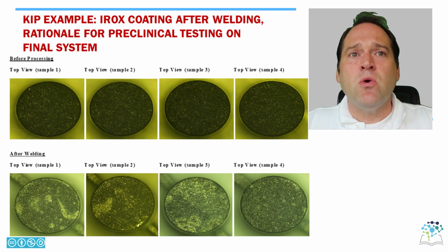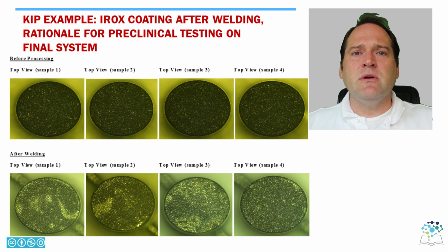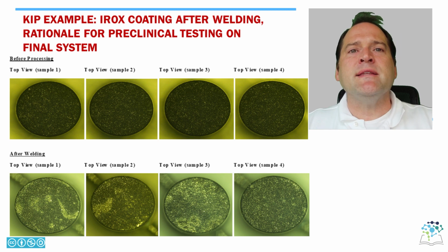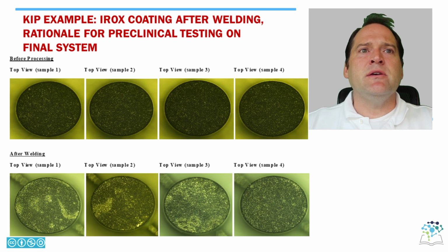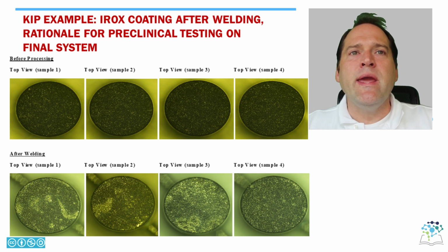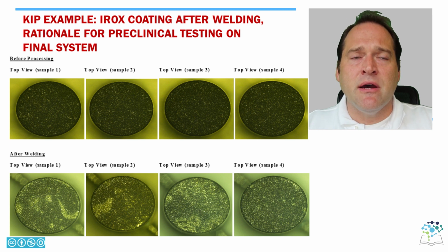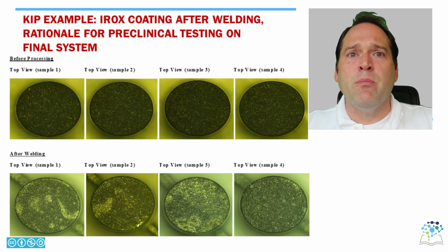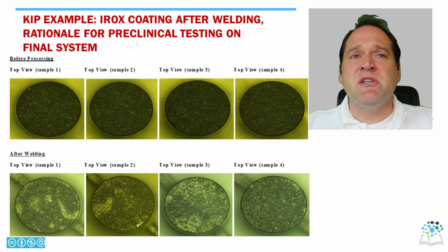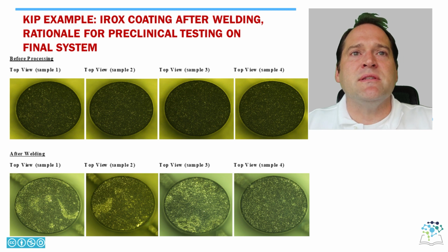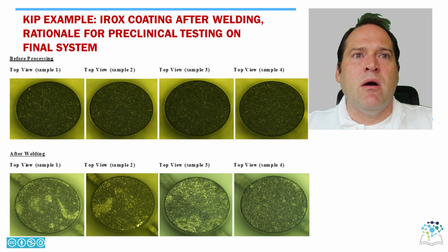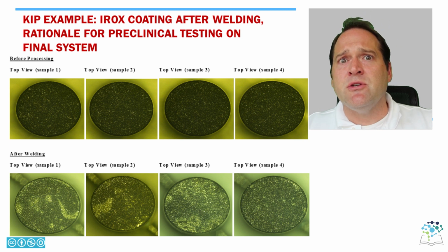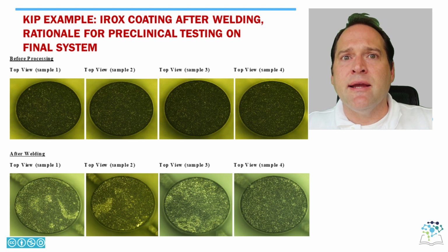And on the top row, it's quite beautiful, but one of the reasons why they don't only look at individual components, but want to look at the full end system the way it's intended to be used in humans, is what you see in the bottom row. We got electrodes in that were coated with iridium oxide, but to some extent we have to create a connection to them to go back to the implantable pulse generator. This was originally done with a weld joint, and specifically a heat weld. And what you'll see in the bottom row is the changes in those coatings from the provider after we did a heat weld. In this particular case, you see a marked change in color and ultimately a marked change in function due to being welded at a high temperature.